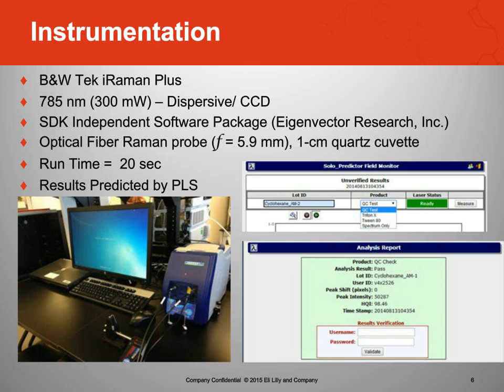In this case, I have a screenshot. You have a drop-down menu for the testing that would occur. Obviously, we do a QC test on a daily basis. The operator or analyst would pick Triton or Tween 80 as far as which material they'd be measuring. And then they click measure, and it'd measure and produce a result. And that result shown here, again, this is a QC check that we did on cyclohexane. It would show pass or fail, and then a second person verifier would verify the results.